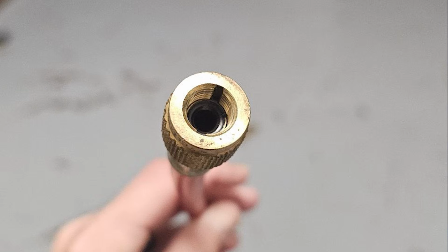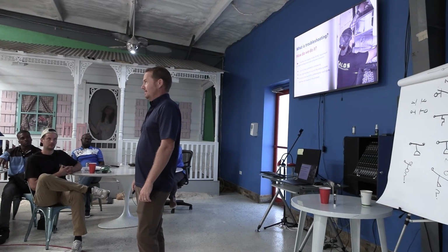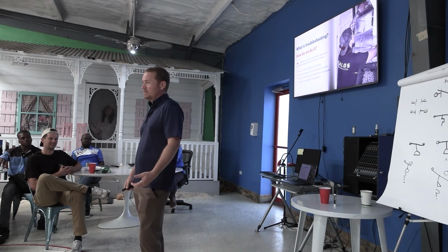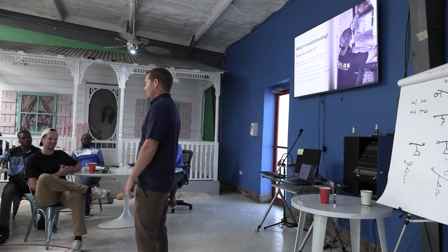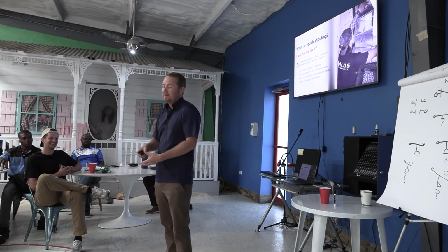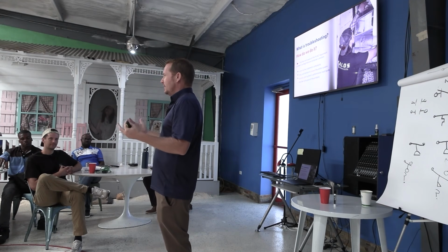And so they're reading 0, or they'll do the thing of, man, I put like a bunch of Freon in this thing and ain't nothing changing. I'm like, what? Did you use a scale? Like, how much did you put in? No, I don't know, I just put a bunch in and ain't nothing changing. I'm like, you don't put a bunch of Freon in and ain't nothing changing. That doesn't work. I don't know what you're talking about. And again, I'm not making fun of anybody who's new, because I get it. I understand how that happens.